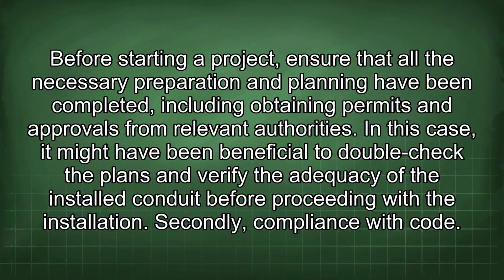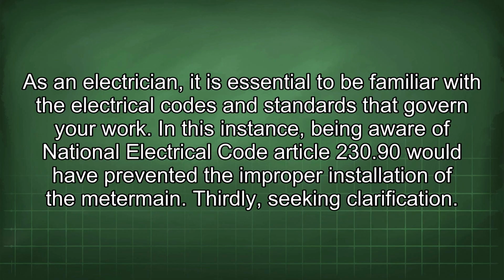In this case, it might have been beneficial to double-check the plans and verify the adequacy of the installed conduit before proceeding with the installation. Secondly, compliance with code. As an electrician, it is essential to be familiar with the electrical codes and standards that govern your work. In this instance, being aware of National Electrical Code Article 230.90 would have prevented the improper installation of the meter main. Thirdly, seeking clarification.